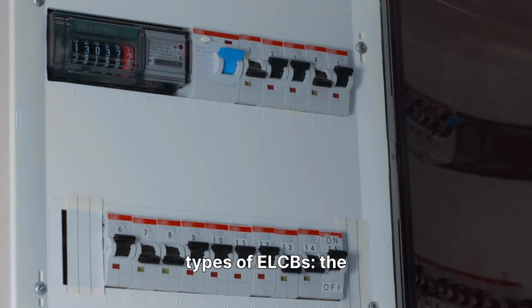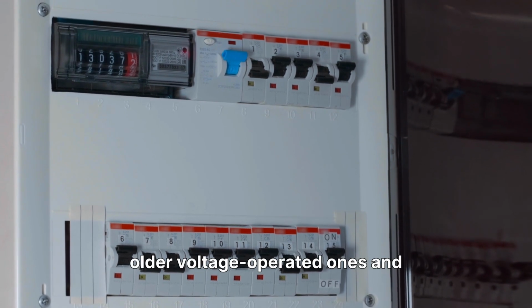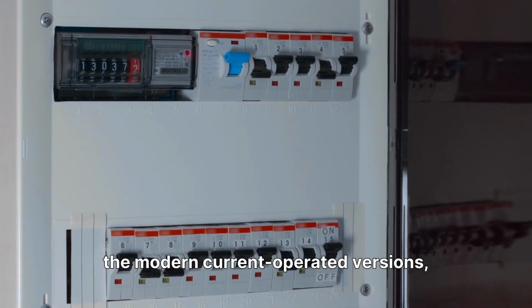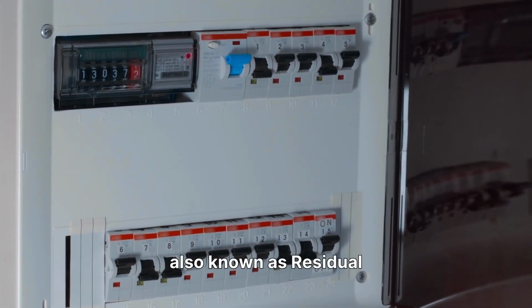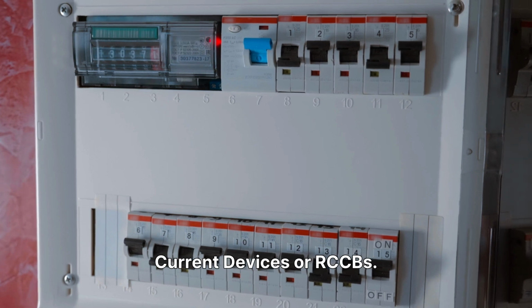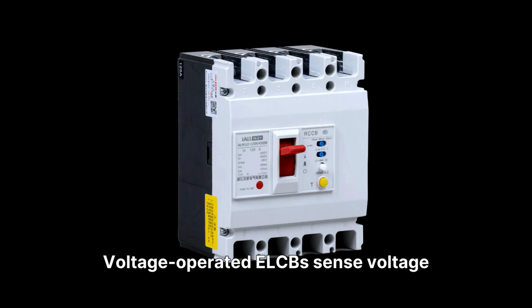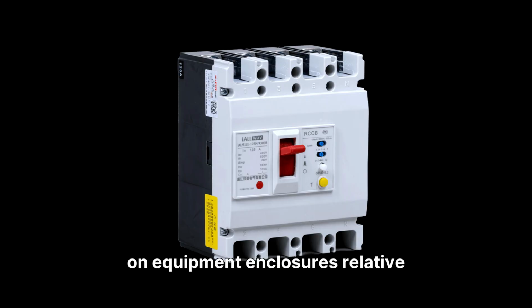There are two main types of ELCBs: the older voltage-operated ones and the modern current-operated versions, also known as residual current devices or RCCBs. Voltage-operated ELCBs sense voltage on equipment enclosures relative to ground and trip if it exceeds about 50 volts, but they are largely replaced by more sensitive current-operated types.